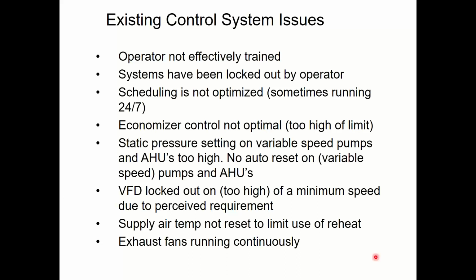A lot of times the system gets locked out by the operator. They log into the computer and they force something to do something it wasn't supposed to do. It's usually not because they're being dumb or being jerks. It's because something wasn't right in part of the building. They forced it to make the problem go away for that moment in time. And then either they didn't realize forcing that thing to happen caused other problems, or they completely forgot about it, right? And they never went back to fix it.